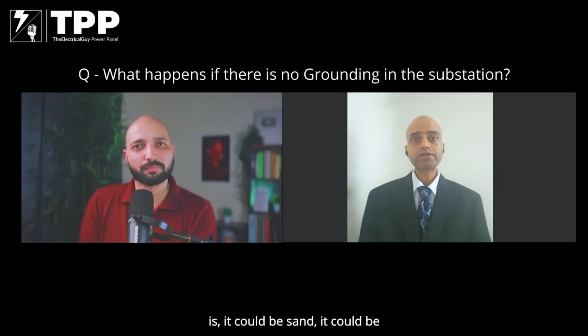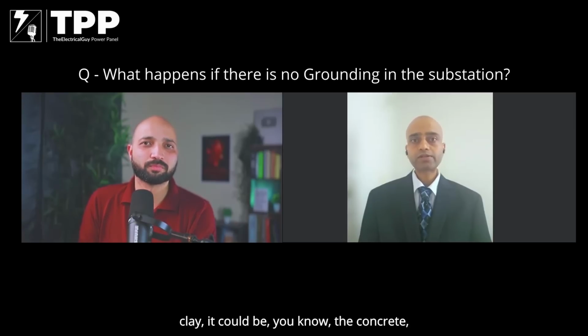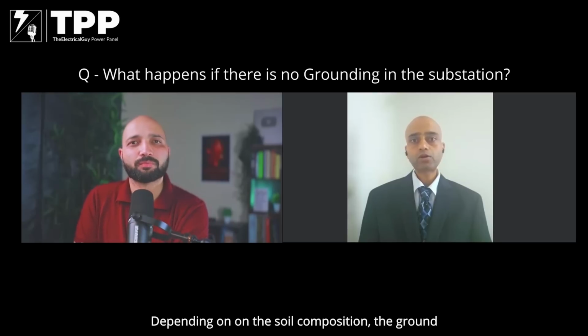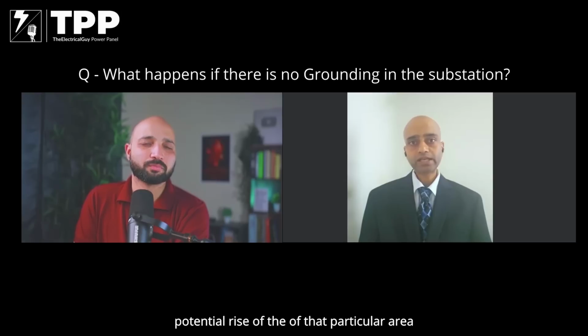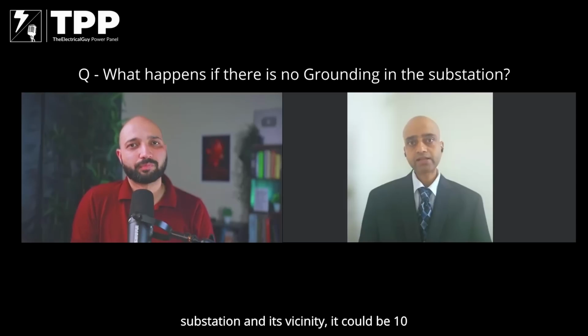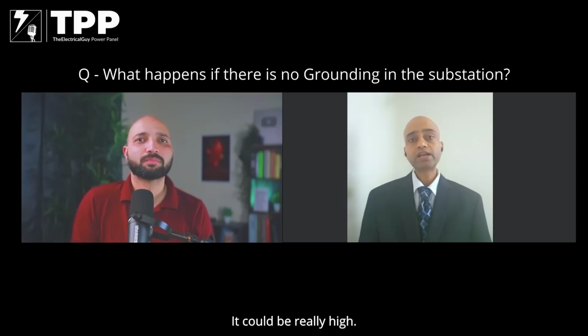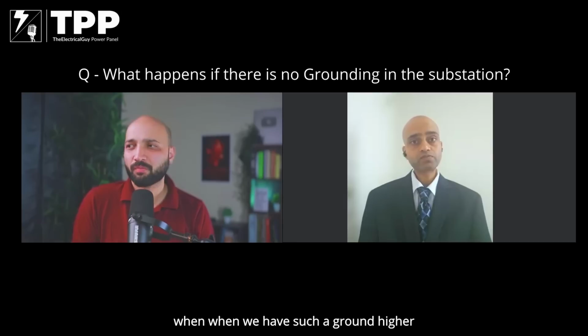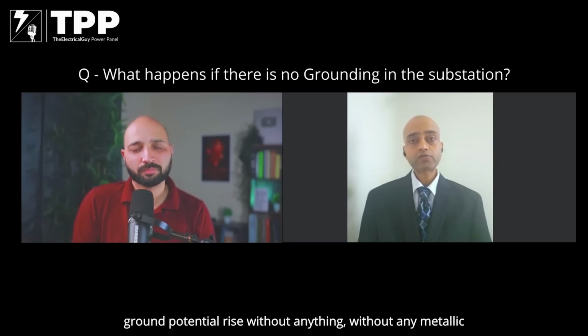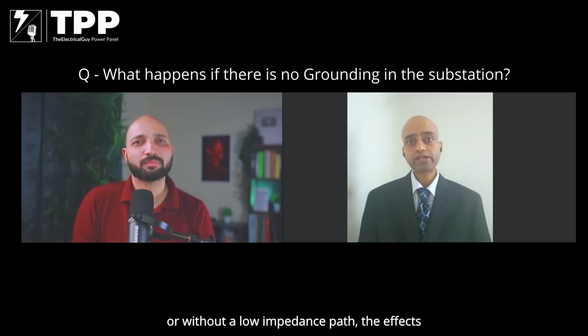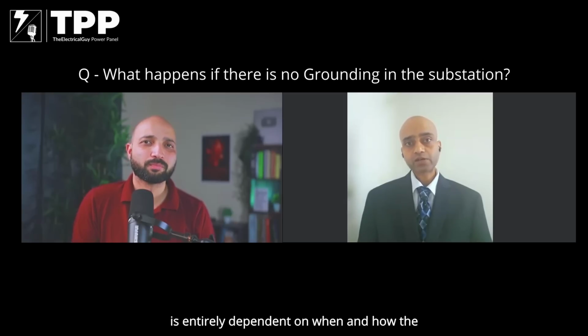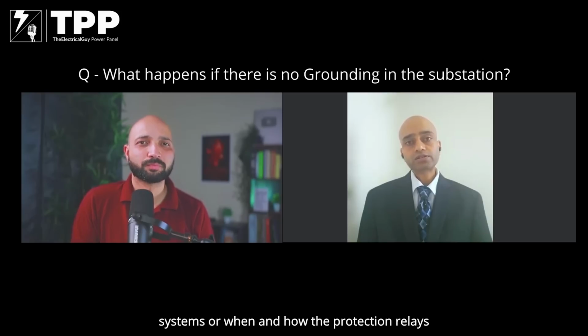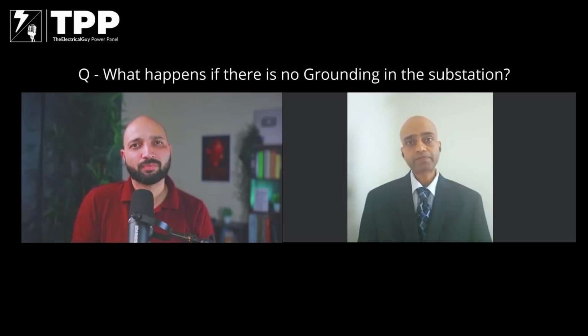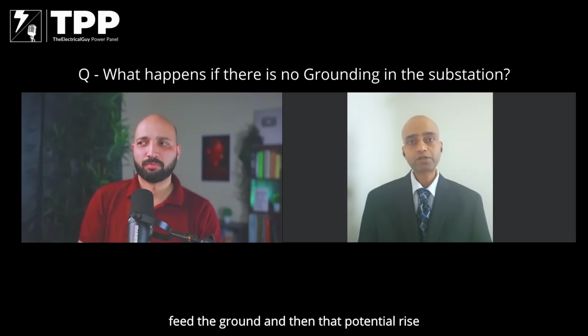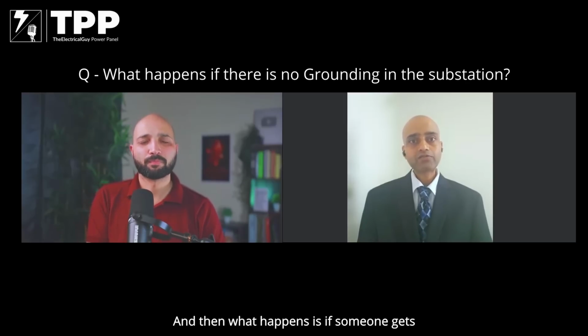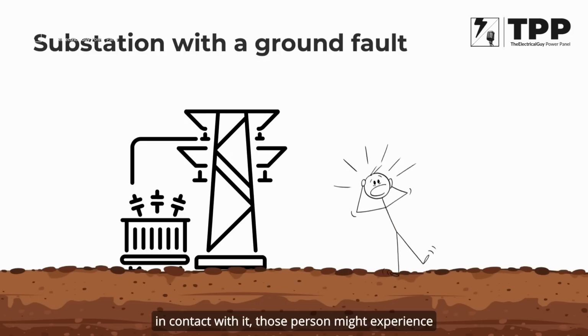Now, depending on what type of soil it could be, sand, clay, concrete, asphalt, depending on the soil composition, the ground potential rise of that particular area at the fault location, for example within the substation and its vicinity, could be really high. Without a metallic or low impedance path, the time for those effects to subside is entirely dependent on when and how the protection relays operate. If there is a delay in operation, then the fault will feed the ground and that potential rise will be sustained. And if someone gets in contact with it, that person might experience an electric shock.